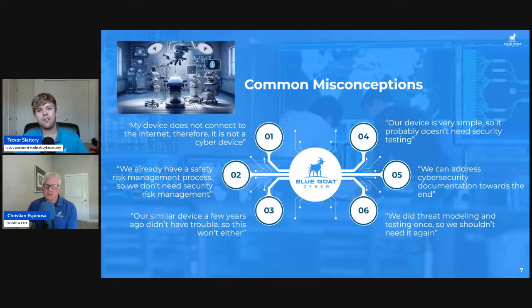Well, we can address cybersecurity documentation towards the end. Again, this is not something you want to wait to the last minute for. As you're going through the cybersecurity documentation at the end, you might realize, oh, we don't have our cybersecurity requirement tests, so we'll just go back and test our cybersecurity requirements. Oh, we didn't develop our cybersecurity requirements. We can try to add them on now. Well, this is going to take us another 6 months to try to develop the device with these requirements in mind. It's very important to try to address this early and often.